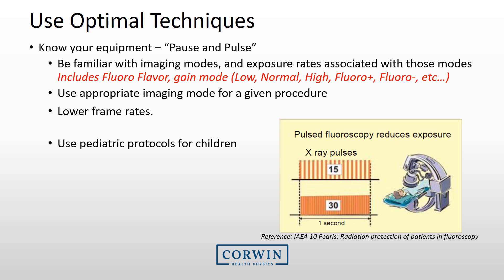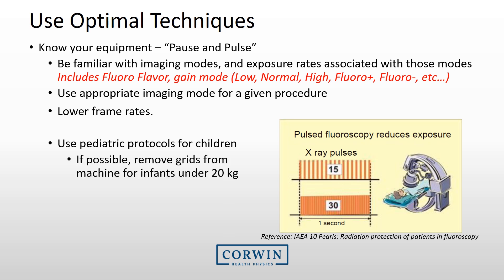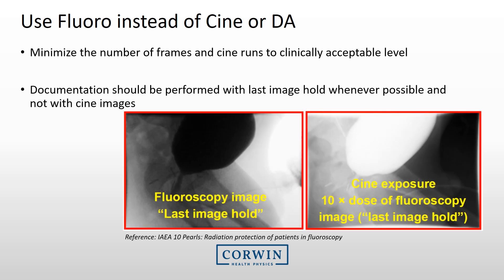Use pediatric protocols when children are imaged, including lower frame rates and increased filtration. For children under 20 kg, it is recommended that the grid be removed and an air gap technique be used instead. When acquiring images, minimize the number of digital acquisitions and cine runs to a clinically acceptable level. Cine and digital acquisitions can have exposures 10 to 100 times greater than fluoroscopy, so whenever possible use the fluoroscopic last image hold instead.